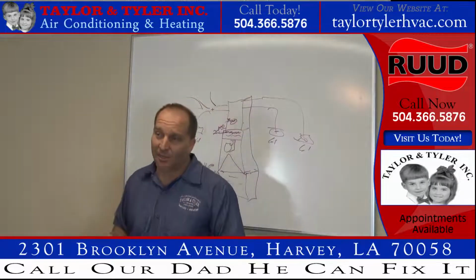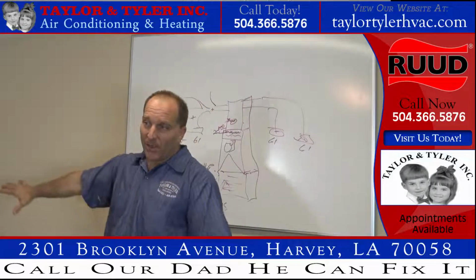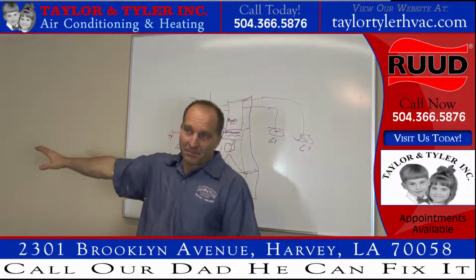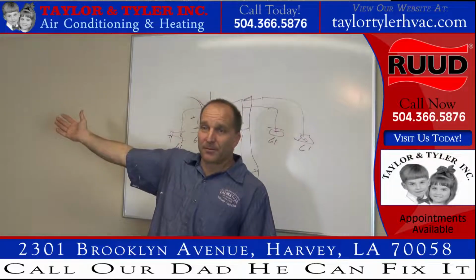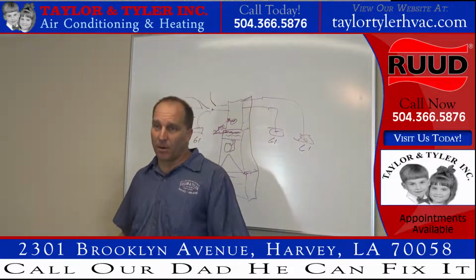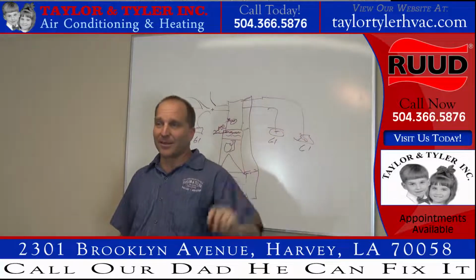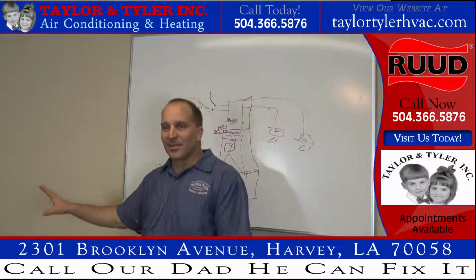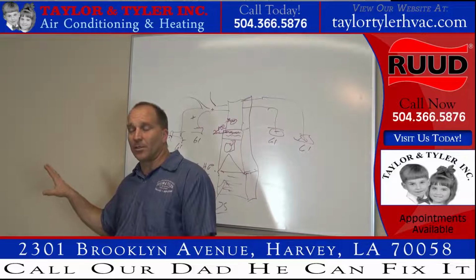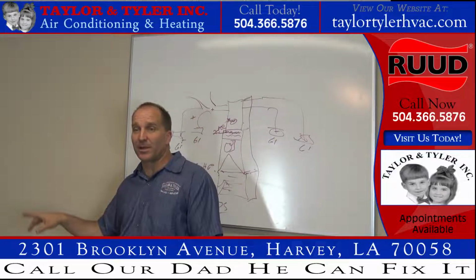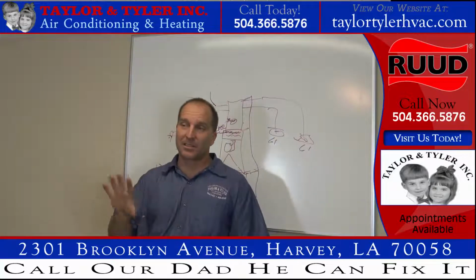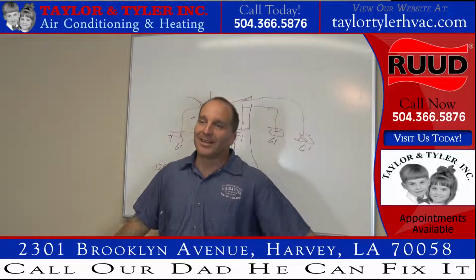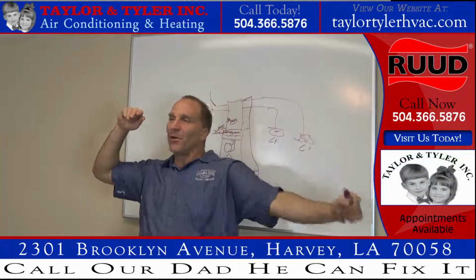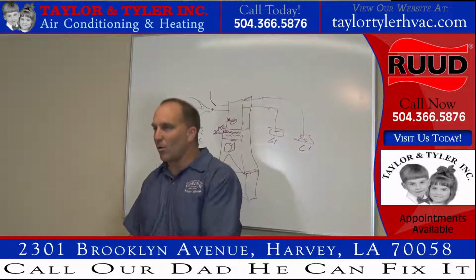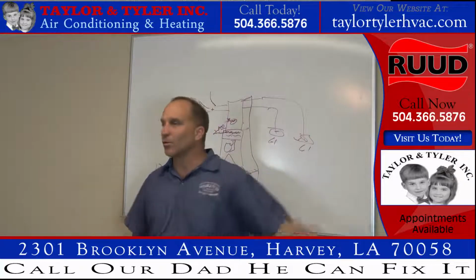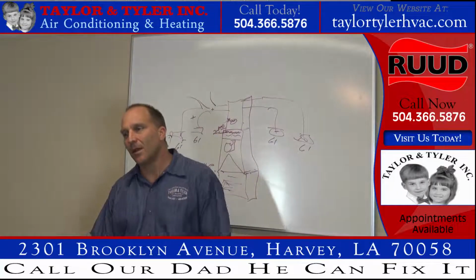We didn't even install it. But Joe Blow installed it. He grabbed the wrong coil. He's got a 2417 coil. He's got a 3-ton condenser. He's got a furnace that naturally blows 1600 CFMs of airflow because it's a 417 for 1600 CFMs. He's got 1600 CFMs of airflow running over a 2-ton evaporator coil with a 3-ton condenser trying to push refrigerant through that coil. That can happen.